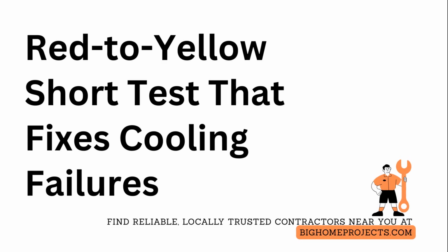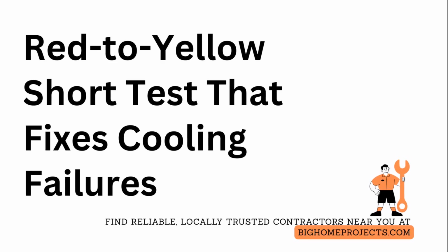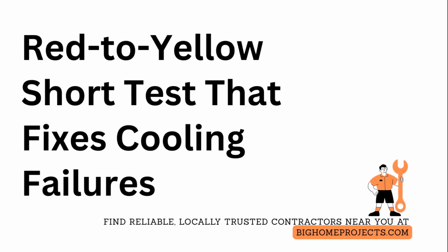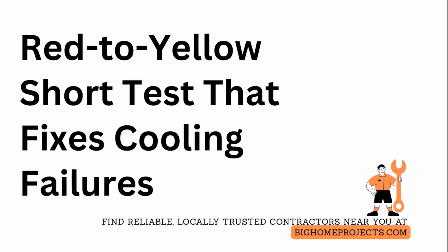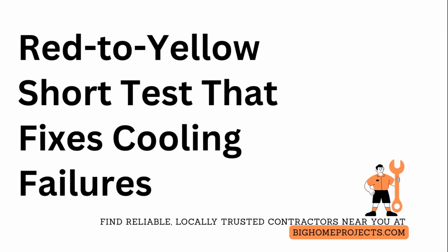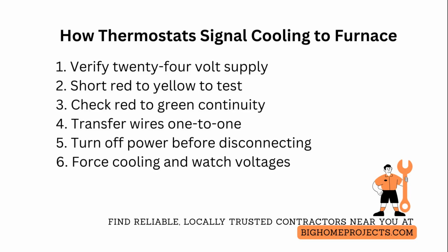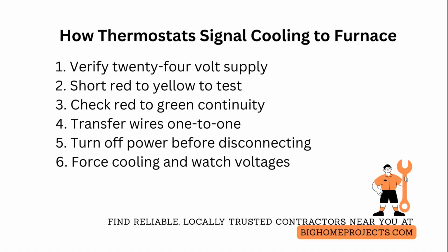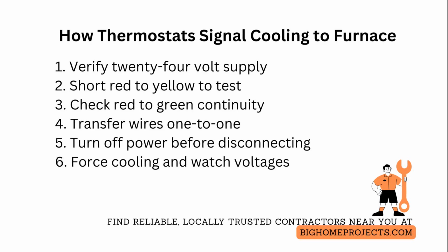Thermostat wiring tells your furnace to start cooling when the thermostat connects the 24-volt hot wire to the correct control wires so the air conditioner and blower receive power. The thermostat typically has a red wire that is the 24-volt supply, a yellow wire that signals the compressor contactor, and a green wire that calls for the blower fan. When you set cooling at the thermostat, it internally ties red to yellow and green in the correct sequence, so both the condenser and indoor fan run.